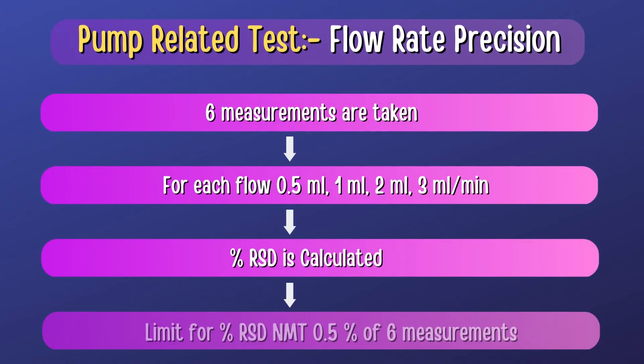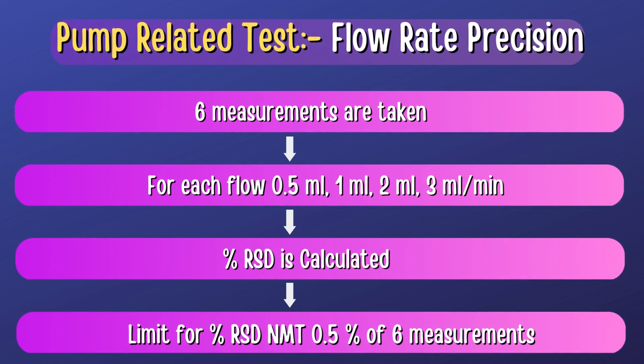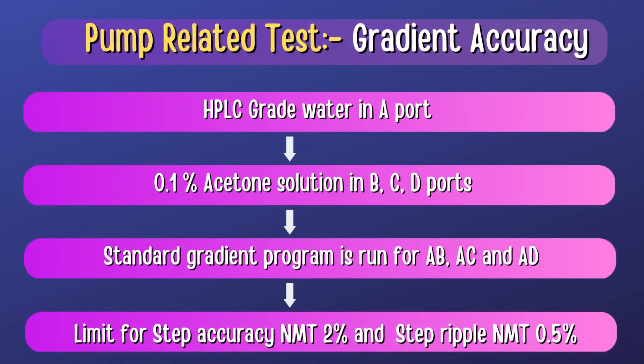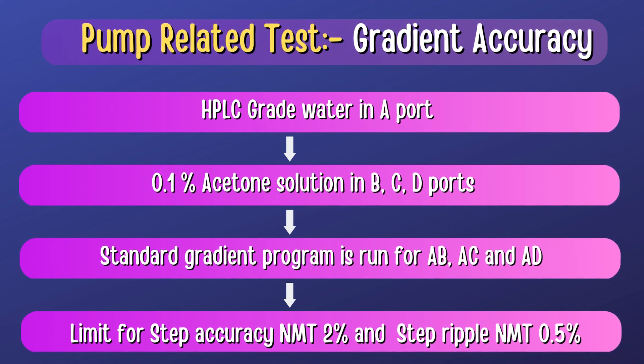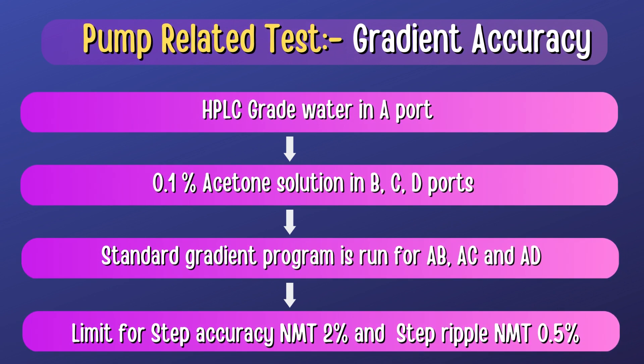For Flowrate Precision, 6 measurements are taken for each flow rate and %RSD is calculated. The limit for %RSD should not be more than 0.5% for 6 measurements. For Gradient Accuracy, HPLC grade water is used in port A and 0.1% Acetone Solution in ports B, C, and D, and a standard gradient program is run for A-B, A-C, and A-D channels. The limit for step accuracy should not be more than 2% and the limit for step ripple should not be more than 0.5%.